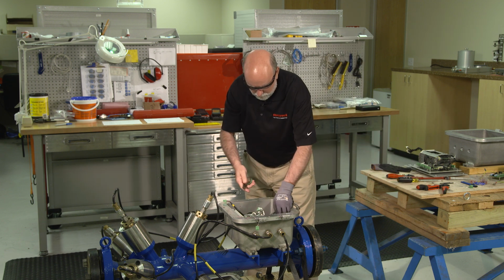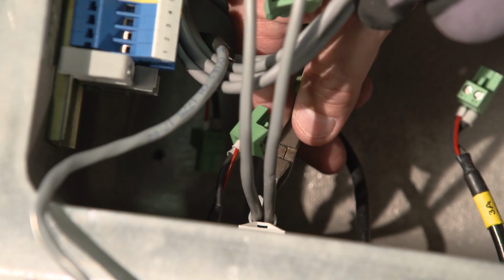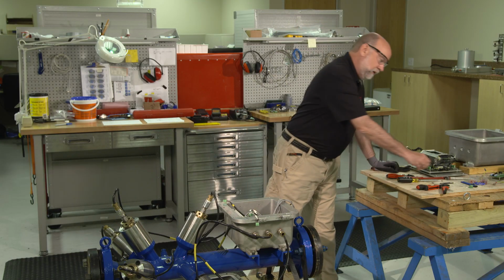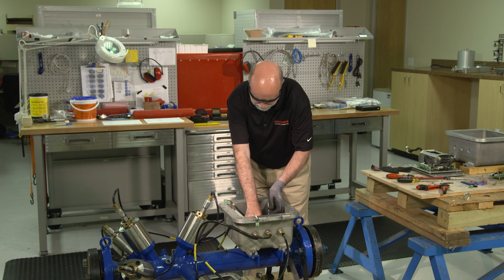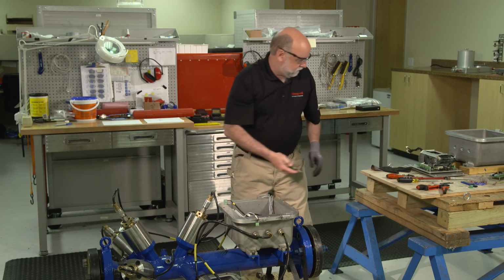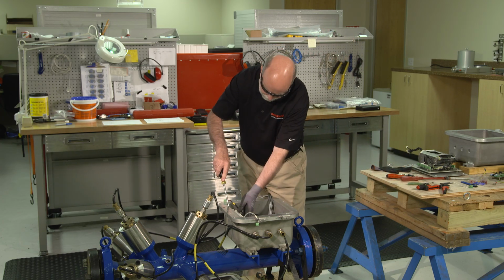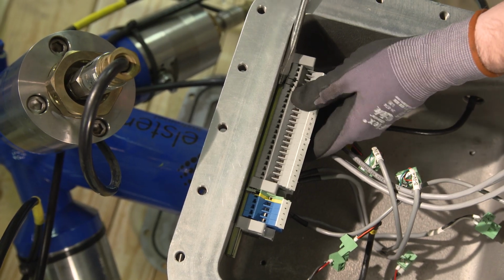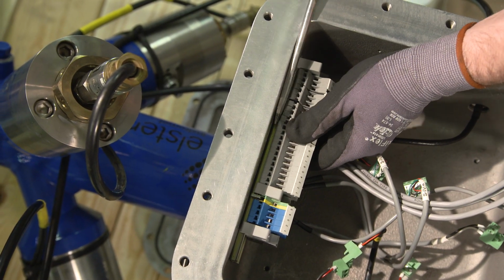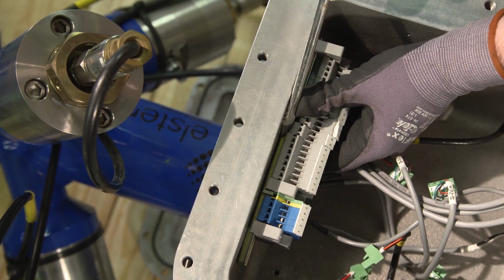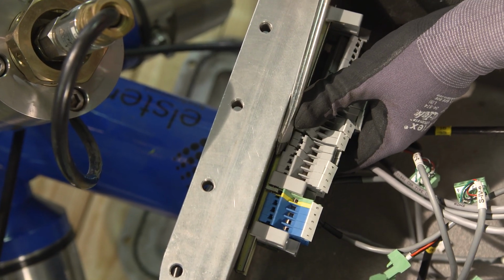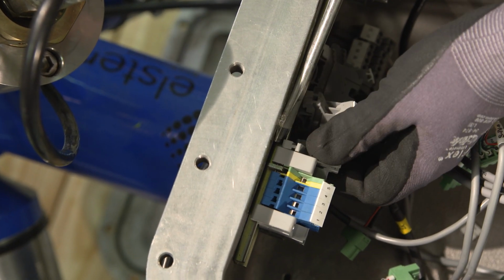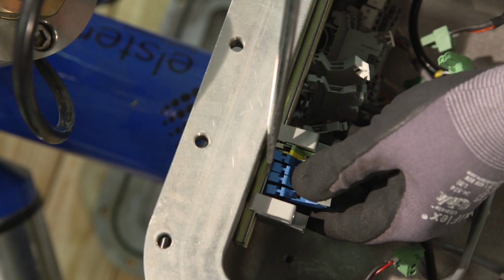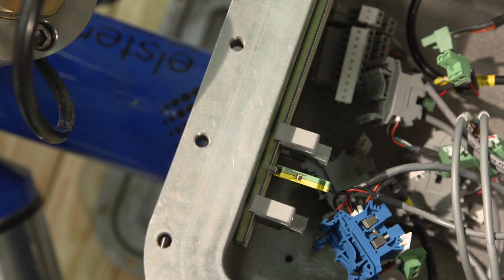Typically, these boxes have a lot of tie wrap mounts and wire ties, cable ties, where the wires have been tied into the box to make them neat and keep them out of the way. You can cut any of those tie wraps loose that you need to remove the wiring harness. Next, we're just going to take a large screwdriver and pop these terminal blocks loose from the DIN rail. Again, you don't have to worry too much about keeping these in order or anything like that. If the numbering strips get popped off, you can just basically discard all of that.